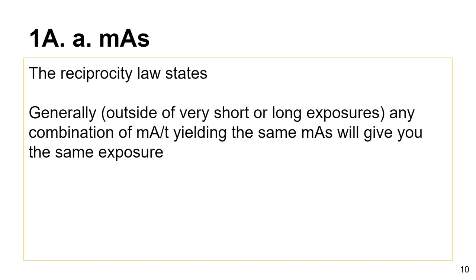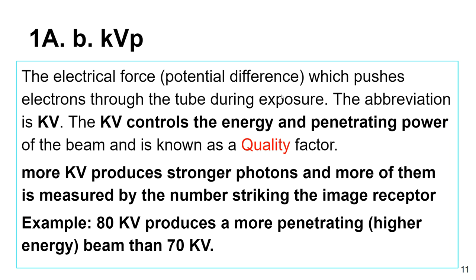Of course, you can only increase mA so much — maybe 300 or 400 stations; in CT you have about 1,000. You're also restricted by your filament — in other words, your focal spot when it comes to mA. In the lab, you may have noticed it'll switch automatically from a small to a large focal spot when you change to a certain technique.